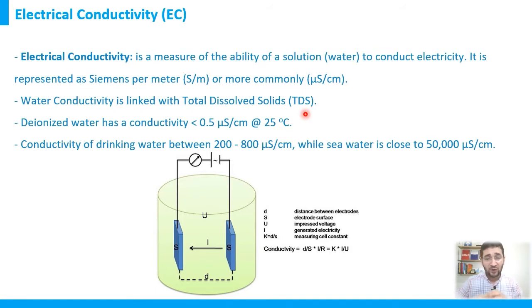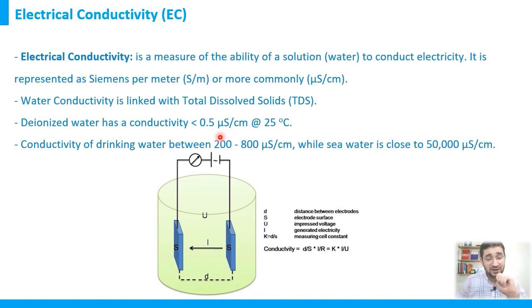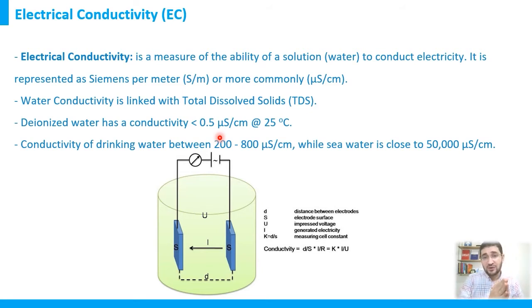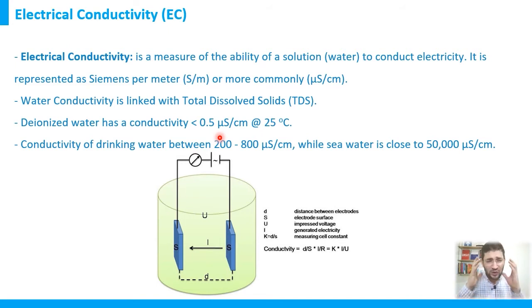To have a scale of reference, deionized or distilled water has a conductivity of less than 0.5 micro-S per centimeter at 25°C. Temperature is mentioned here because, like pH, electrical conductivity is dependent on temperature. When we have higher temperature, pH goes down, and conductivity increases. So always keep that in mind — you cannot measure pH or conductivity without accounting for the temperature at which the measurement is taken.